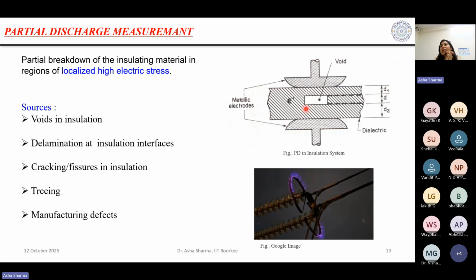One thing I want to clear here is that whenever we talk about the insulating material used in the power system, we are always very much concerned about the permittivity or the dielectric constant. If I say some dielectric constant is good for that high voltage, it means the dielectric constant must be very high. If I talk about solid, liquid, and gaseous, gas has a dielectric constant of 1, liquid has more than 1, and solid has more than 1 and more than the liquid as well. So if an air bubble is present here, it has a permittivity or dielectric constant of 1. The material which we are using here must have a permittivity more than 1. There is a difference in the permittivity between the two materials.